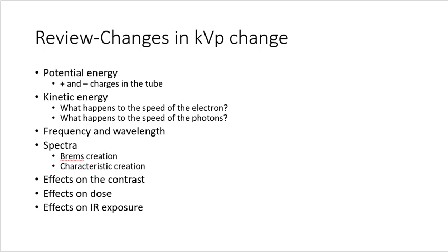The difference between what your machine puts out and what you have set has to be within plus or minus 5%. Some of your textbooks are going to say different things. Some will say 3 to 4 kVp, some will say 6 kVp. And when there's differences, then you need to consider a couple of different things. If there's differences between textbook authors, chances are they're not going to be that specific on the registry.